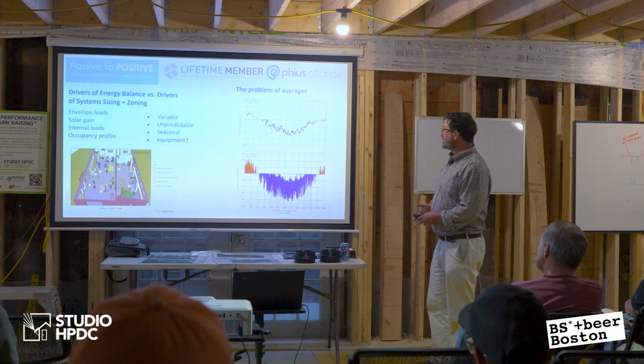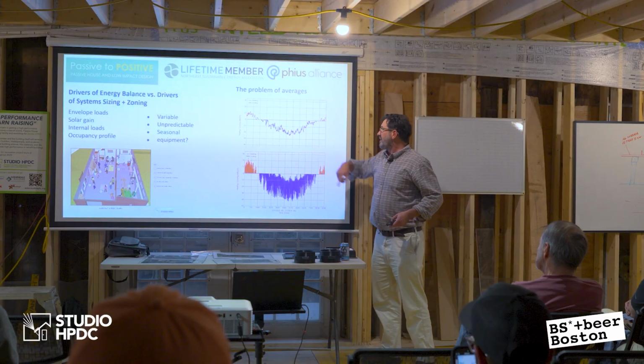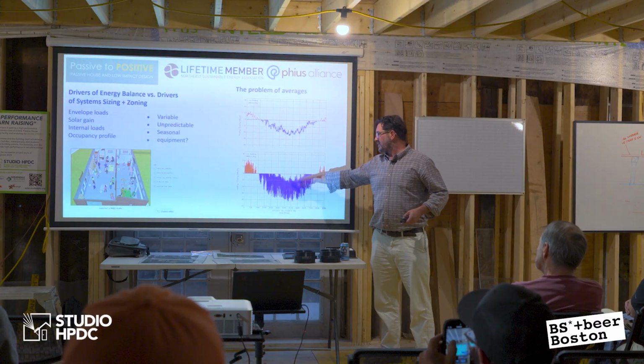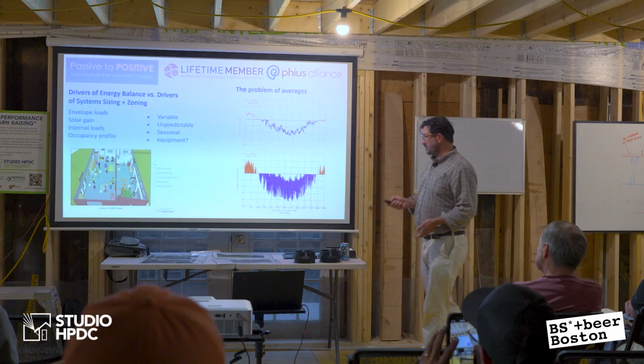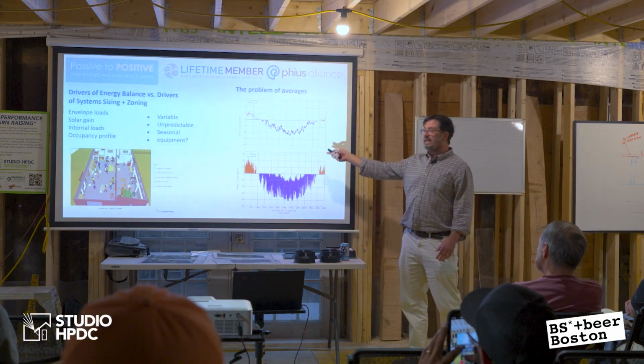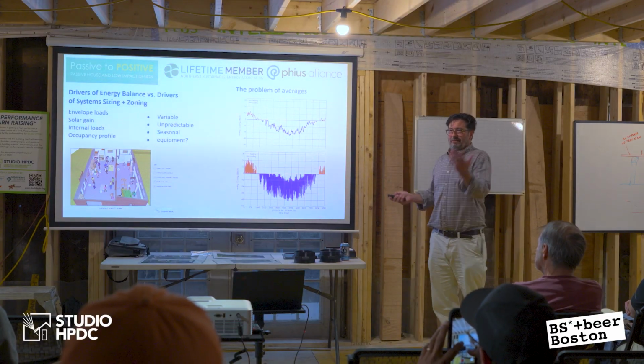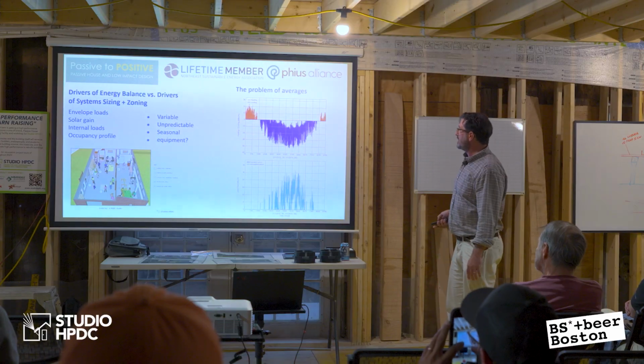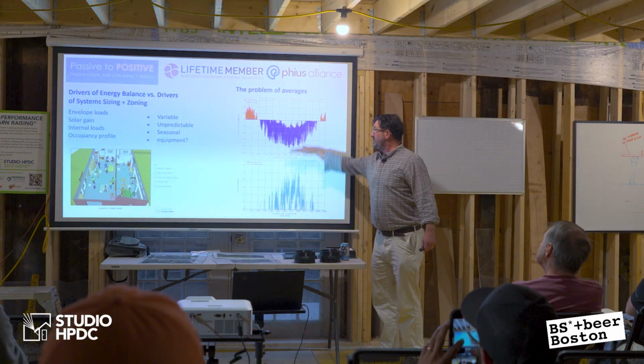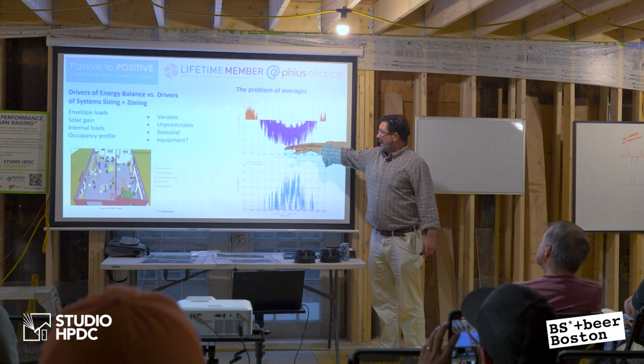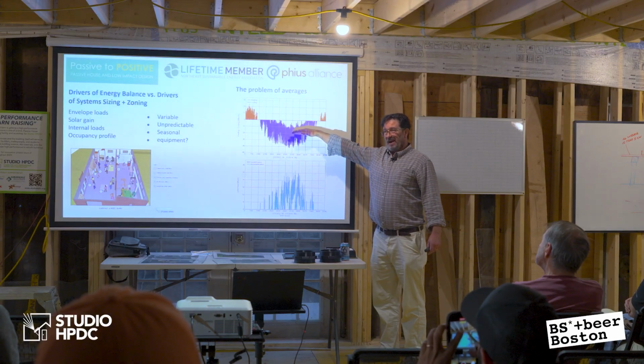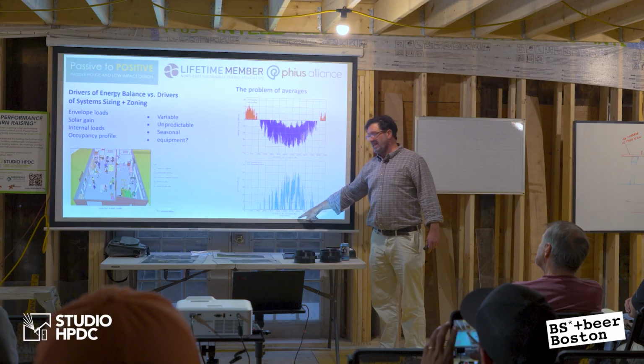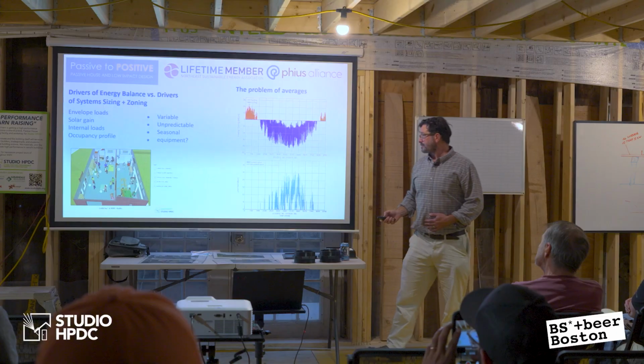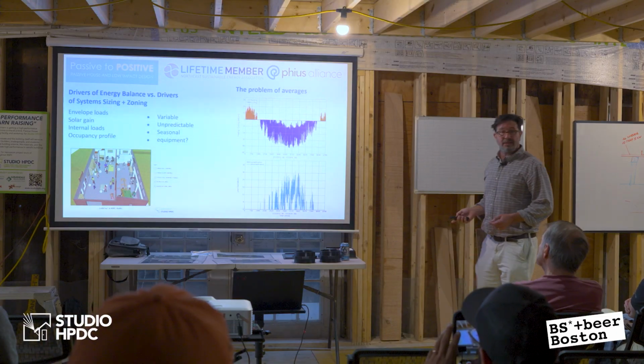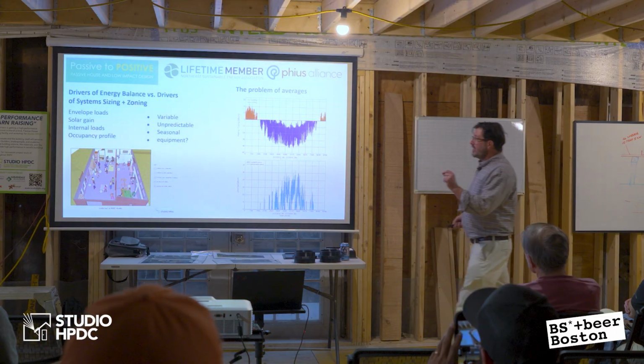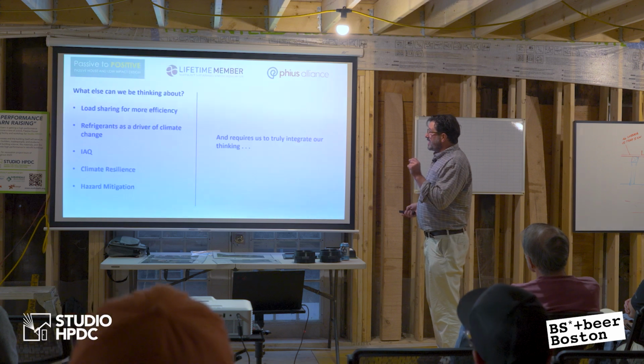So the problem of averages, even if it's daily averages, this is the reality. And that's the thing that Ross has to be accountable for, while we're really happy with the top one, you know, great, we just heat it that much per day, whatever. Then the problem of latent loads. Even if you get the full hourly, which is double the average, then the latent loads are substantial. Another doubling in Washington, D.C. Now this is interesting, right?